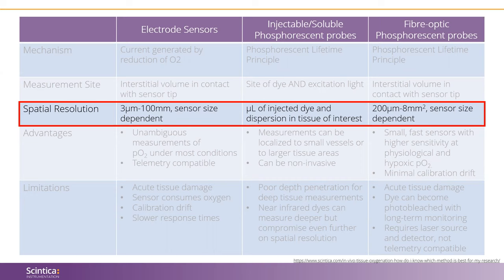With respect to spatial resolution, electrode sensors can measure a wide variety of area sizes, from the smallest at three microns up to 100 millimeters, and sensor size varies depending on what you're measuring. Injectable dye probes will measure whatever microliter of dye is injected and to the extent of its dispersion in the tissue. Fiber optic phosphorescent sensors are mainly invasive for in vivo applications, measuring areas from 200 microns up to 8 millimeters squared. The OxyLite oxygen sensors range in diameter from 230 microns up to 750 microns, suiting a host of tissue monitoring applications where measurement sites vary in size.